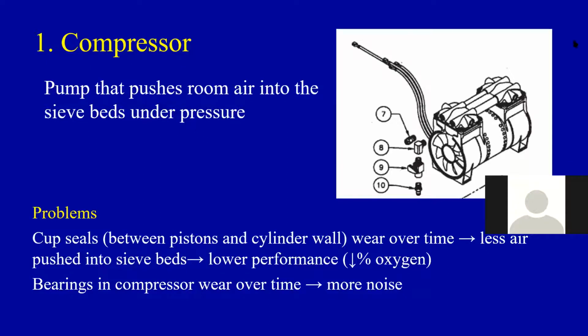And the reason to know about the compressor is that there's a couple of parts in the compressor that can wear over time. And when they wear out, then the concentrator won't be producing as good a concentration of oxygen. And the two parts within the compressor that sometimes wear out are called the cup seals. And the compressor is like a compressor in your car. It's got pistons and it has cup seals inside, and it's also got bearings, like bearings in the wheel of your car, in brakes of your car, and they can wear out over time because they're moving all the time. Sometimes the concentrator then makes a bit more noise than it should, and sometimes you'll be able to detect a problem with the compressor because there's a low oxygen concentration being produced by the concentrator. So the compressor is one thing.